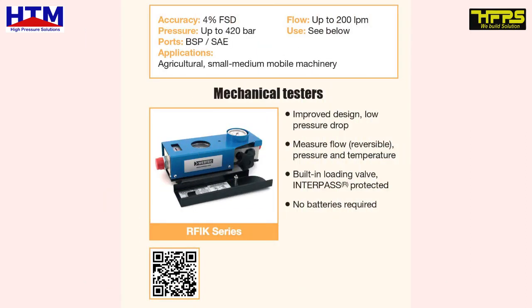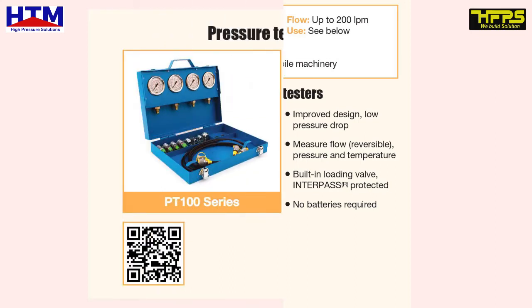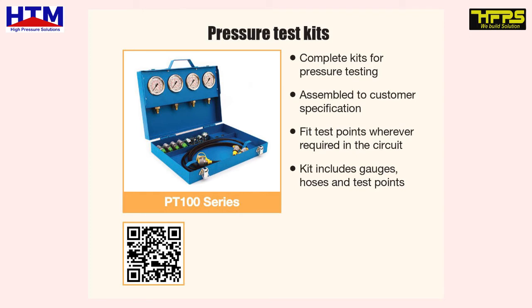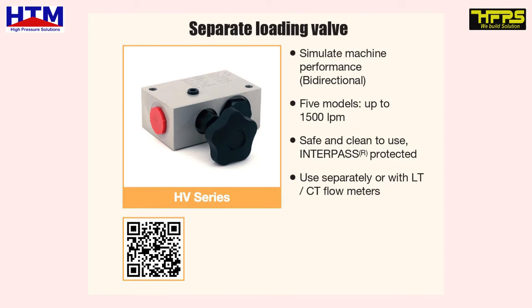Mechanical testers RFIK. Accuracy 4% fs. Can handle up to 200 lpm: 30, 60, 120, and 200 lpm. Purpose to measure flow, pressure, and temperature. Built-in loading valve with bypass protection. No batteries required. Pressure test kits. Complete kits for pressure testing, assembled to customer specification. Fit test points wherever required in the circuit. Kit includes gauges, hoses and test points. Separate loading valve to simulate machine performance. 5 models available. Safety with bypass. Can be used in LT or CT or FI.